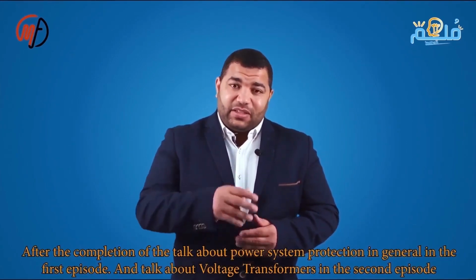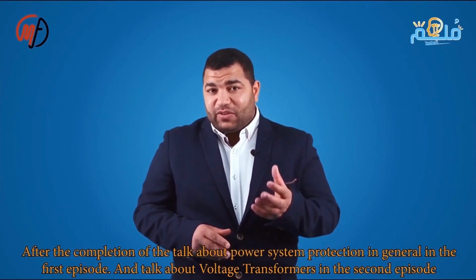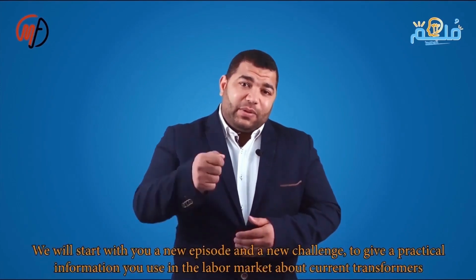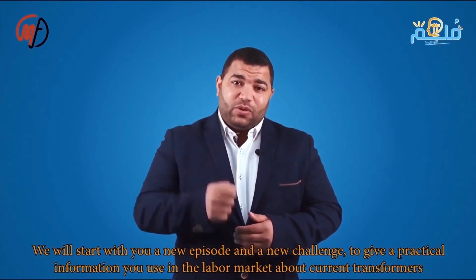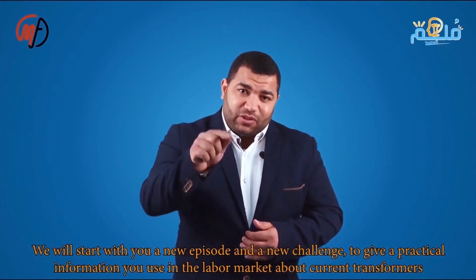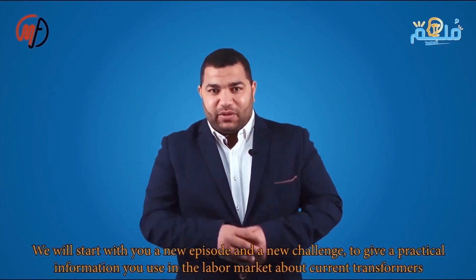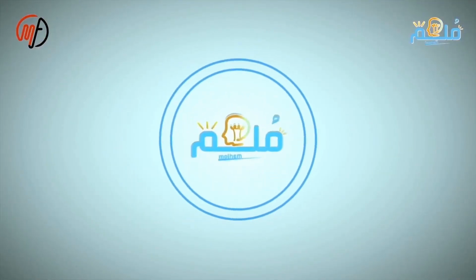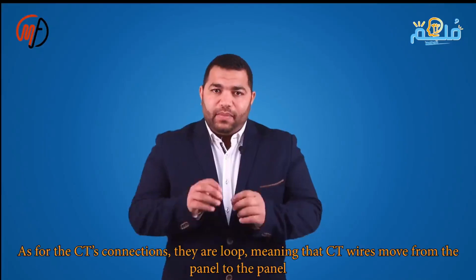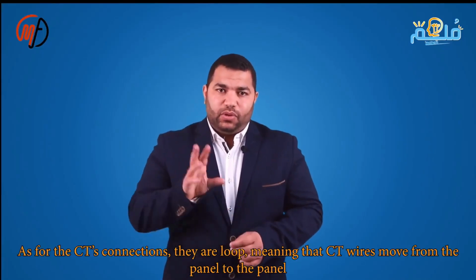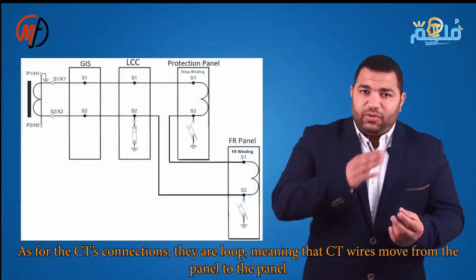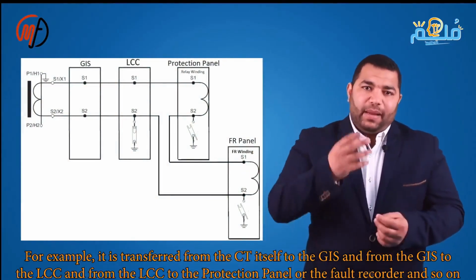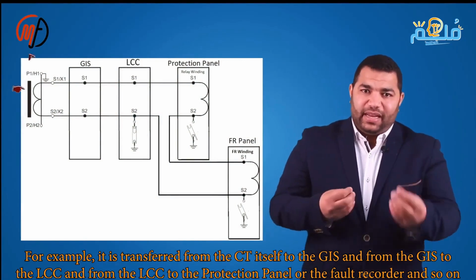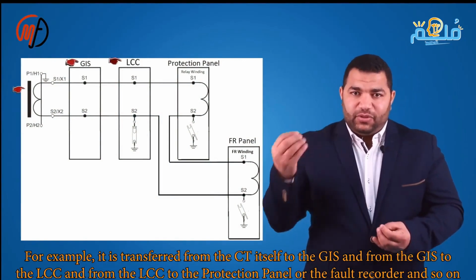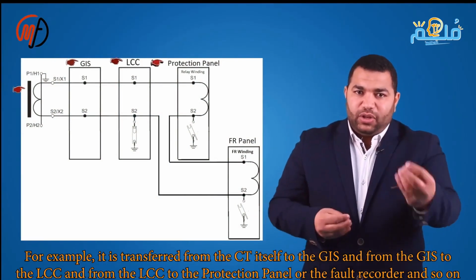Now, after finishing the general discussion in the first episode and talking about it in the second episode, we start with you a new episode, a new challenge, and practical information that will benefit you in the job market about most of the CT connections. They are in the form of a loop, meaning that the CT wire goes from panel to panel. For example, the current flows from the CT to the GIS, then from the GIS to the LCC, and from the LCC to the protection panel or the fault recorder, etc.